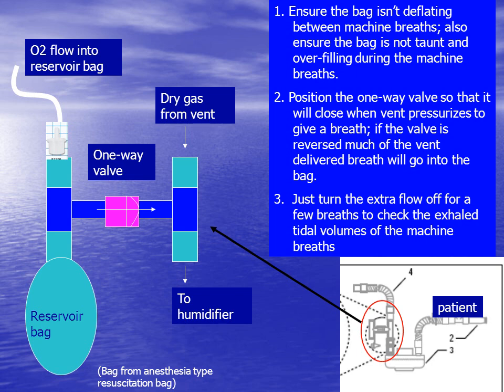In a continuous flow system, you're essentially teeing in a reservoir bag on the dry side of the vent. You need to add the flow on the dry side so that the added flow has a chance to receive humidity. You must utilize a one-way valve so that the PLV doesn't ventilate the bag instead of your patient. And as with most reservoir bags, you want the flow to the bag to be sufficient to keep it inflated. You don't want it to collapse when the patient pulls a breath, but you also don't want flow to the bag to be so high that it pressurizes the bag and shoots flow into the circuit past the one-way valve continuously, whether the patient has tried to pull a breath or not.